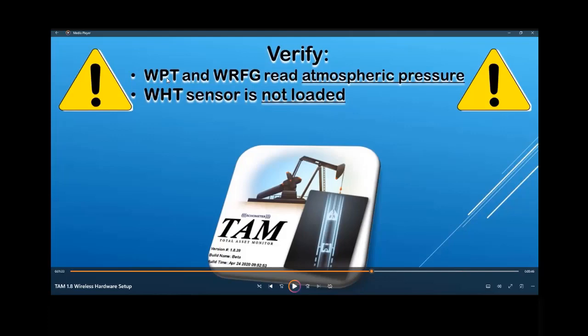Same with the WHT, which stands for wireless horseshoe transducer, used in dynamometer acquisition, or the HT, the wired transducer. You do not want to zero the offset with load on the sensor, on the strain gauges.